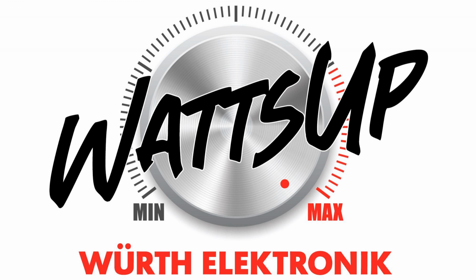However, we need to be aware that it is very likely that high-frequency noise can couple around the ferrite through parasitic capacitance to GND and earth planes. Most EMC standards begin limiting radiated EMI at 30 megahertz, so preventing this unwanted antenna effect of input and output leads is very important. When a ground plane or shielded enclosure is present, noise can couple around a ferrite placed towards the interior of a PCB. In this example, the PARD noise gets around the chip bead ferrites by coupling capacitively through the ground plane and earth to the input and output of the connectors.